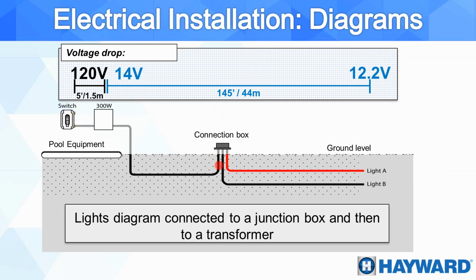And here we can see the junction box, how it is going to be installed above the ground level. So if there is any kind of flooding or something like that, it is not going to get into our junction box because it is totally sealed. And at the same time, that junction box is also meant to be installed outdoors. So it can be installed on a planter, some sort of landscape around the pool, and that's fine. It can rain on it, and even if there's some flooding because of a lot of rain, the connections are safe because it is elevated away from the ground level.